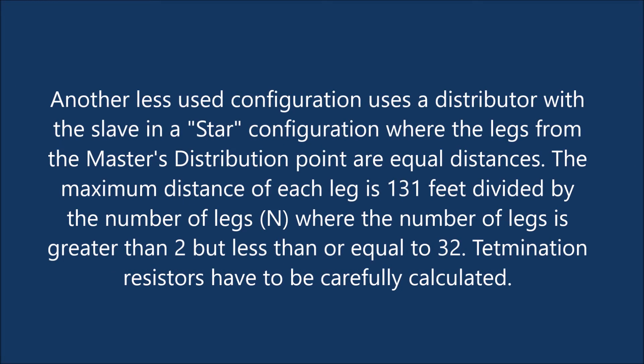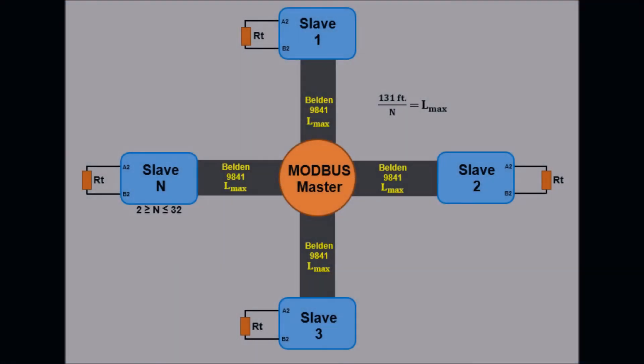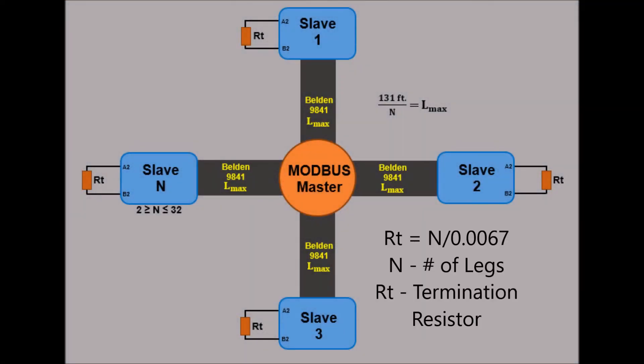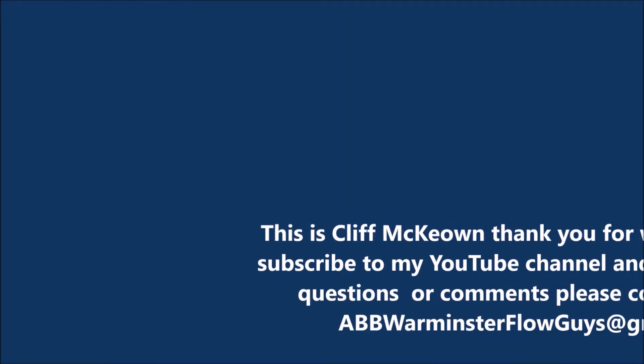Another less-used configuration uses a distributor with the slave in a star configuration, where the legs from the master's distribution point are equal distances. The maximum distance of each leg is 131 feet divided by the number of legs (n), where n is greater than 2 but less than or equal to 32. Termination resistors have to be carefully calculated: RT equals n divided by 0.0067, where n is the number of legs and RT is the value of the termination resistor.